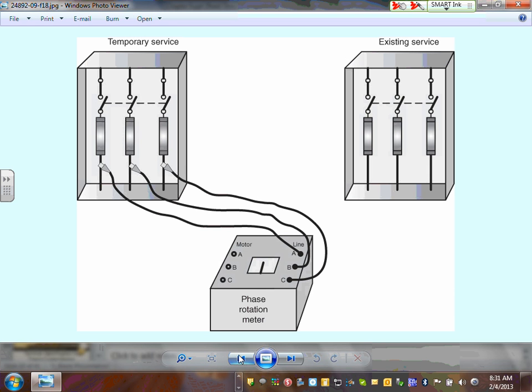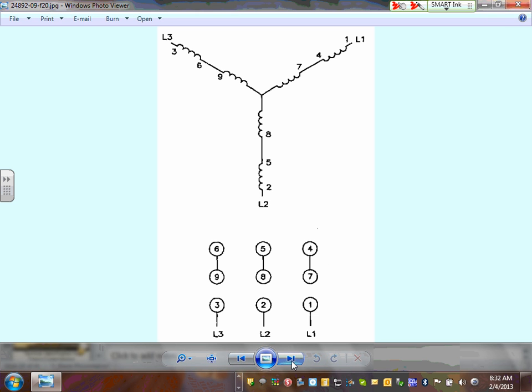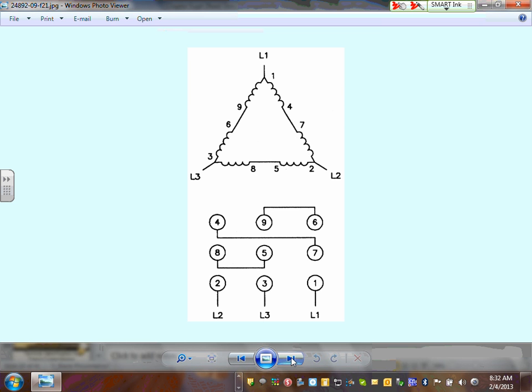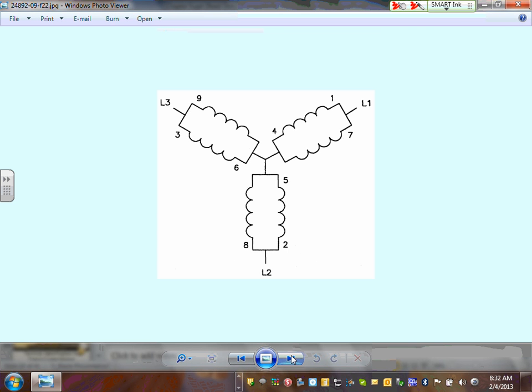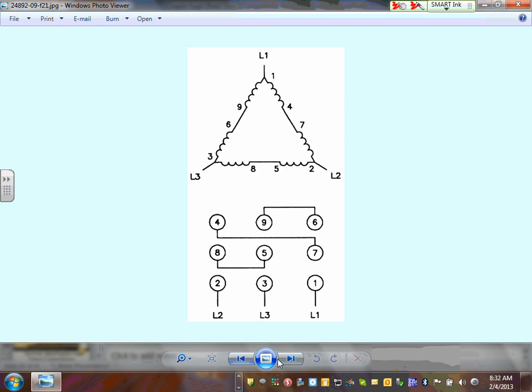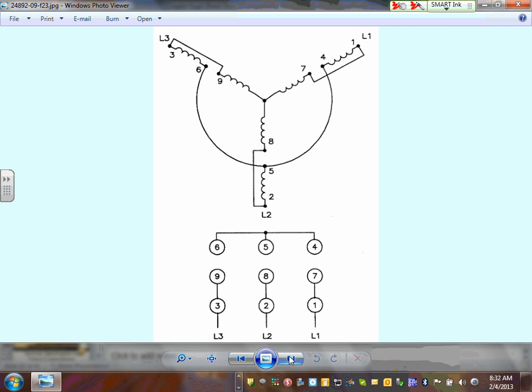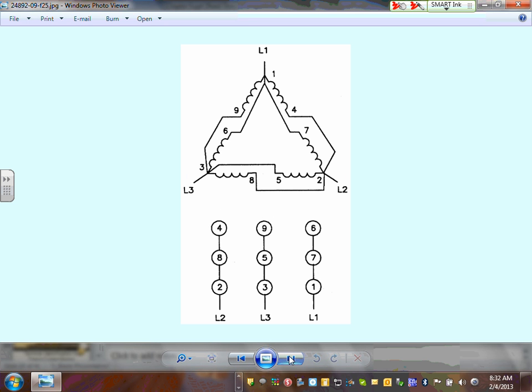That's really good. Remember, you flip any two phases in a three-phase system, what happens to the rotation of the equipment? Reverses it. That's kind of the drawback of the three-phase system. We talked about windings and connection. You can connect your equipment, if you put the coils in series, you get high voltage. If you put the coils in parallel, here's a parallel coil. This is low voltage. Here's the series coil, high voltage. And you guys will read that one. Here's the parallel coil, low voltage. Low voltage again. So we're paralleling the coils. Every time you parallel the coils, you get your low voltage.